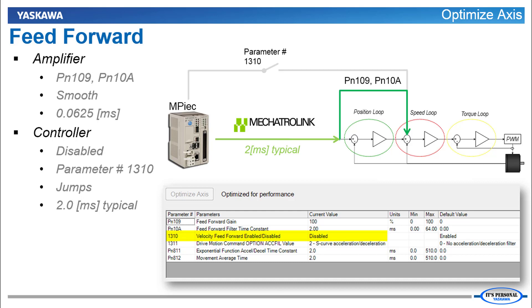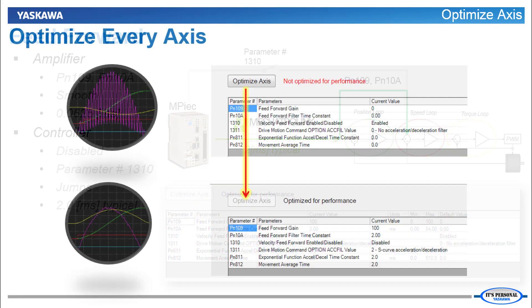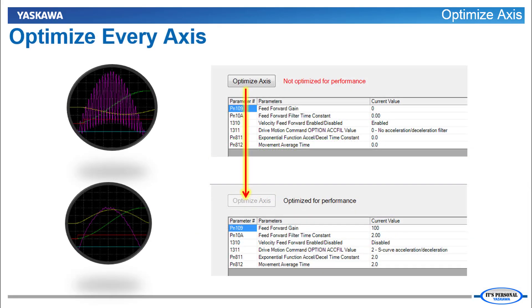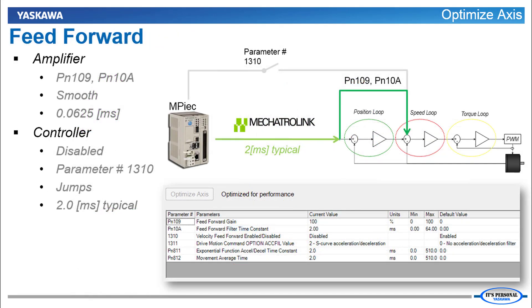After the servo is tuned for high performance, the response to the controller feedforward can result in many small jumps at every Mechatrolink cycle. Each jump produces a surge of motor torque, resulting in higher torque ripple and motor heating. Therefore, the controller feedforward is disabled.